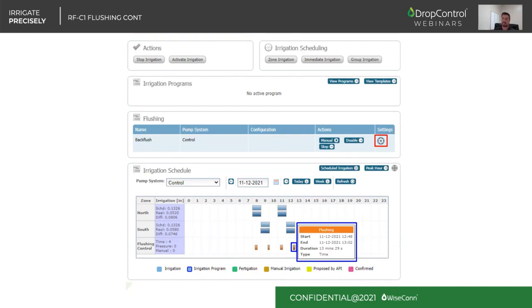So if you have 6 tanks, is flushing from the first one to the number 6. You can disable the flushing feature. So in case you detected an emergency or you are under an ongoing maintenance, you can disable momentarily the flushing feature, and then you can re-enable it back whenever you want. And finally, if there is any cycle or flushing running at the moment in the field, you can stop it remotely. Besides the actions, you also have advanced settings, which we are going to cover in the next slide.